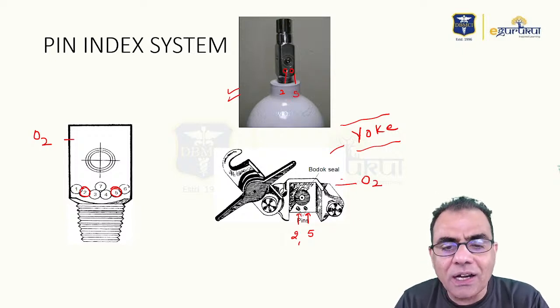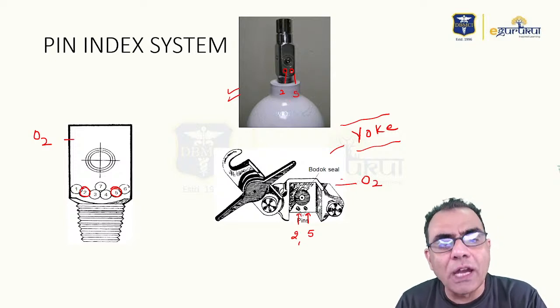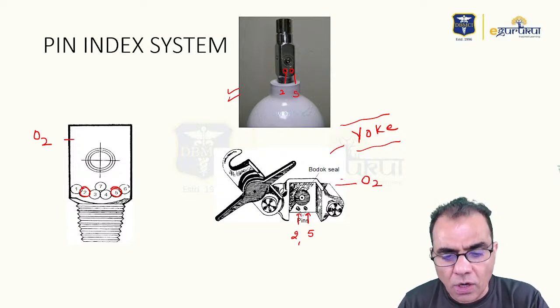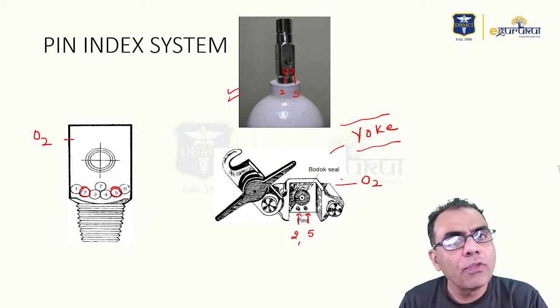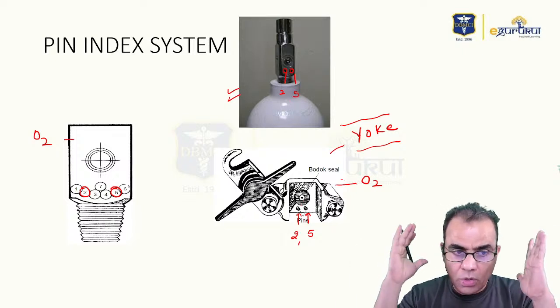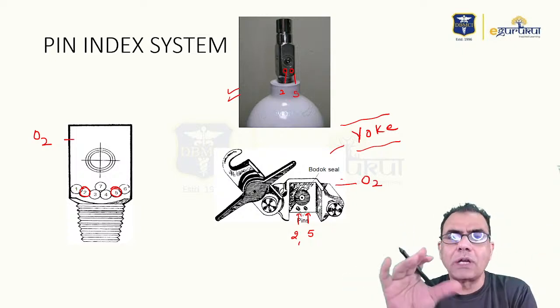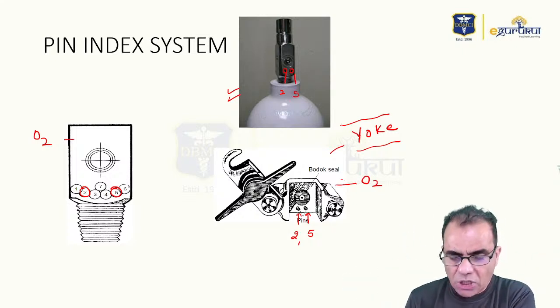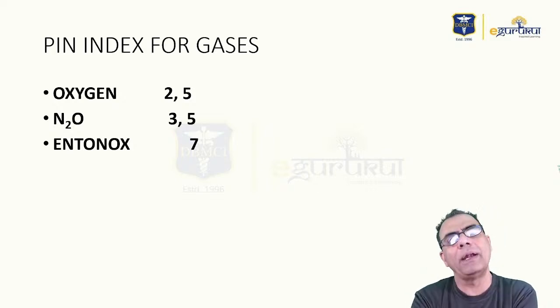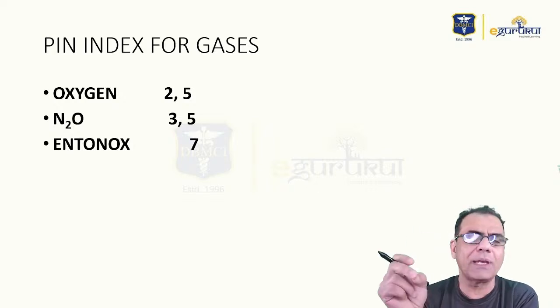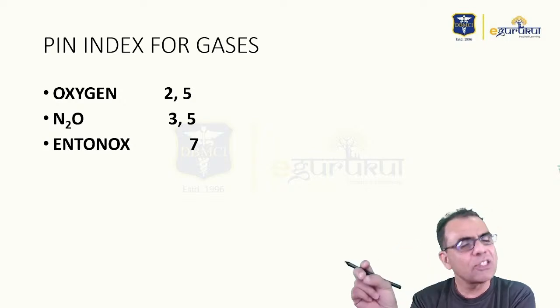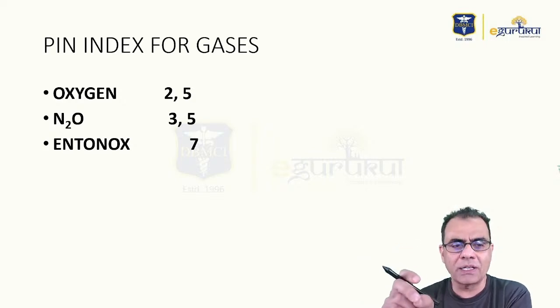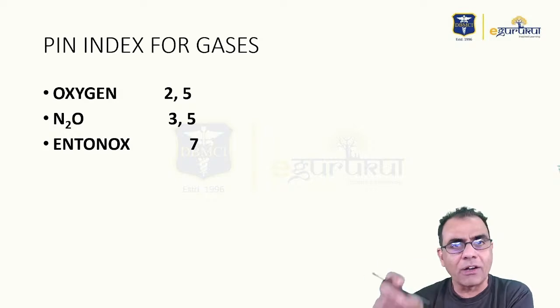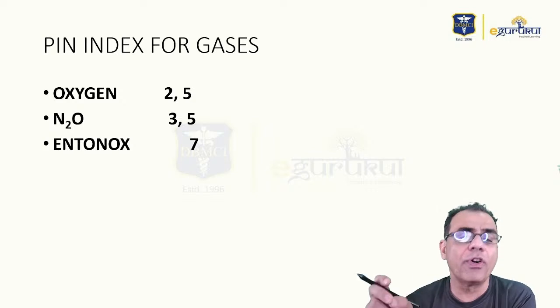For the nitrous oxide cylinder, the pin position will be 3 and 5, and the hole position will also be 3 and 5. So you cannot fit a nitrous oxide cylinder at the place of oxygen. Now, I think you have understood what exactly the pin index system is. So you have to remember the pin index system. What is commonly asked is the significance of the pin index system, and the significance is that it prevents wrong fitting of cylinders. And the pin index position, very often they ask.